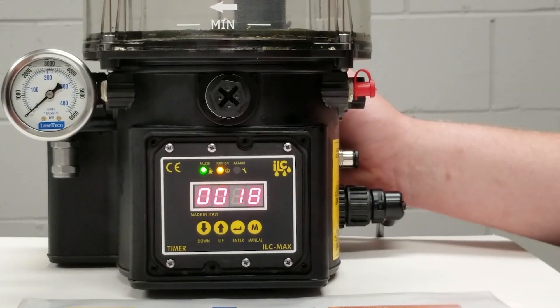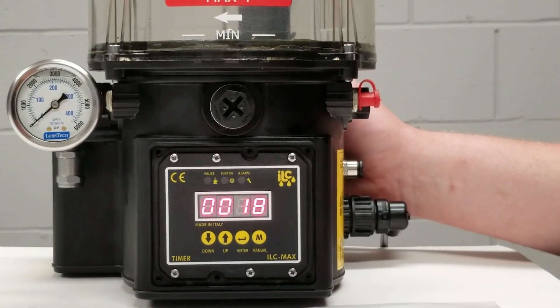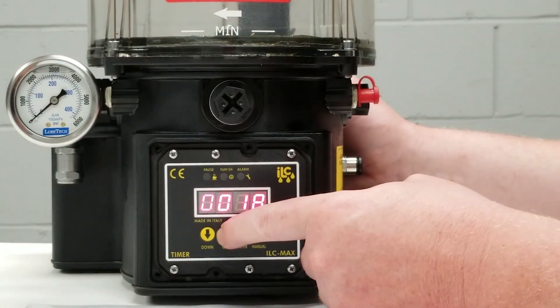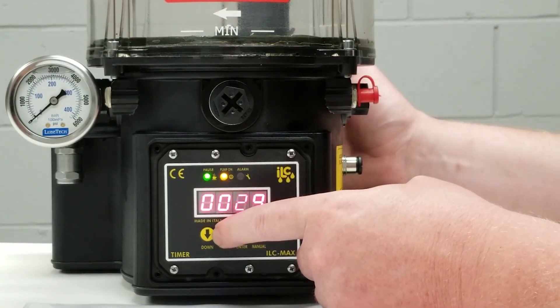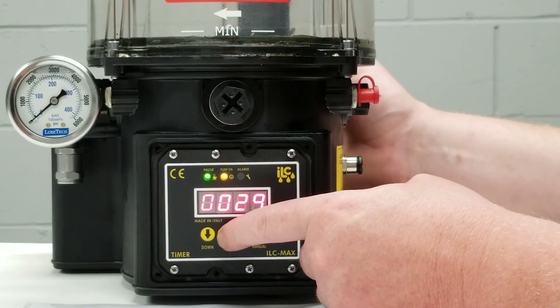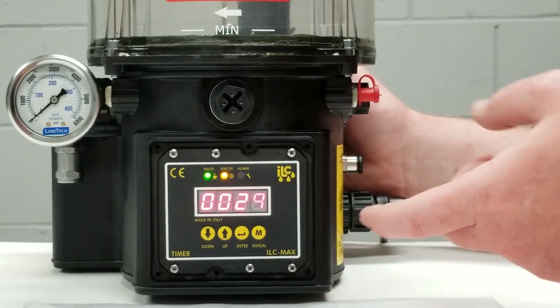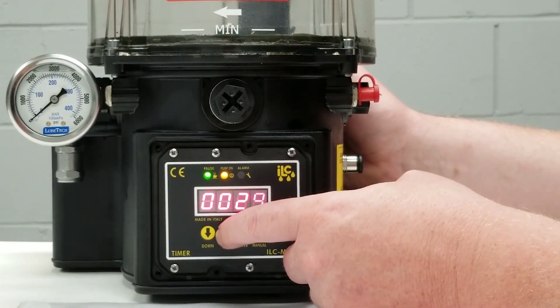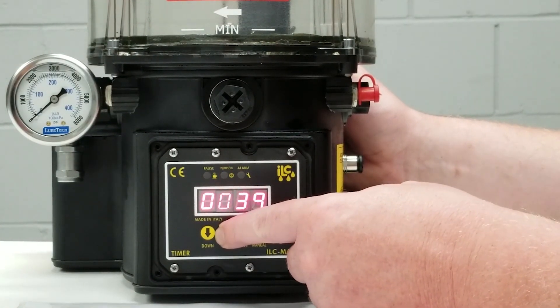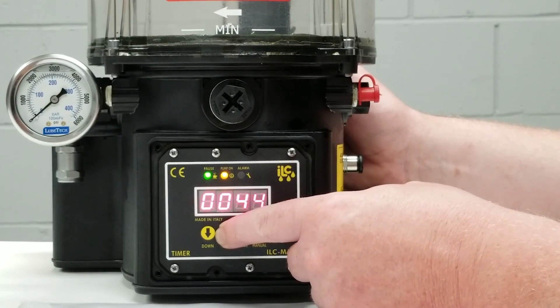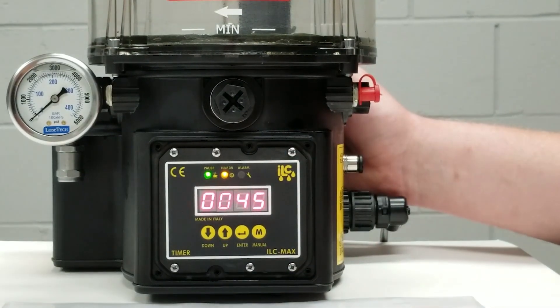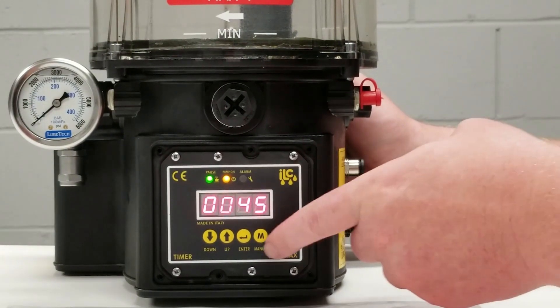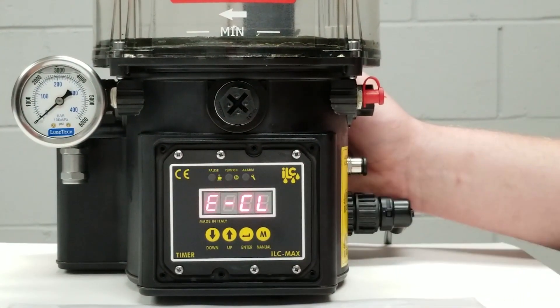So this particular pump is programmed for 18 rotation counts and we can program in more rotation counts. The higher the rotation count, the more lubricant it will deliver. The lower the rotation count, the less lubricant it will deliver. So we're going to change this from 18 rotations. Let's just say we want to change it to 45. We'll program in 45 rotation counts and to exit this again we'll press the M button.